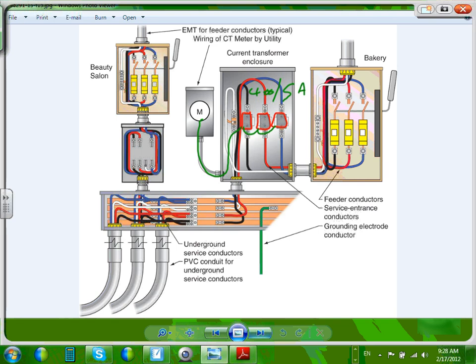And then we have our grounding electrode conductor in the cabinet, and we have to tie the grounding electrode conductor. You're going to be bonding the grounding electrode conductor to the, well, in this case, it's bonded to the enclosure, to the gutter. Any comments, any questions? Yeah, what does the CT cabinet do for the bakery? It's due for the bakery, not the others, because the bakery is the largest load here. It's a 400 amp.